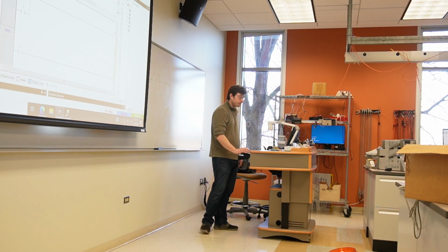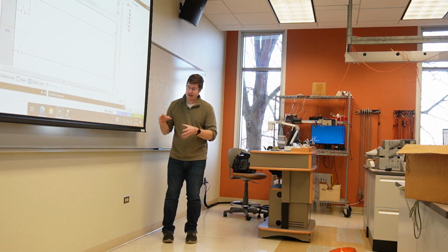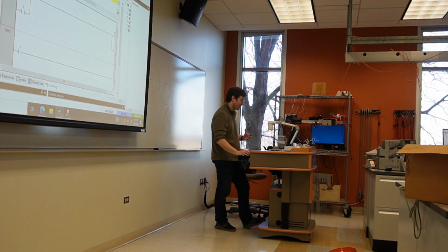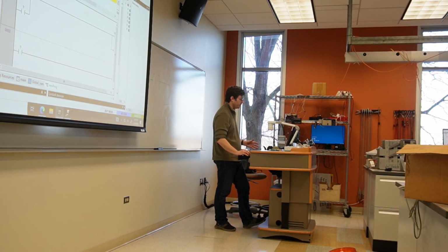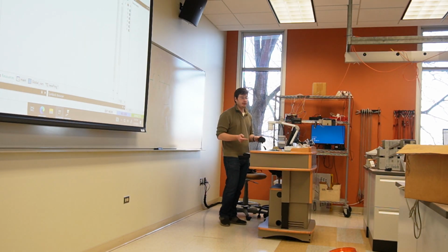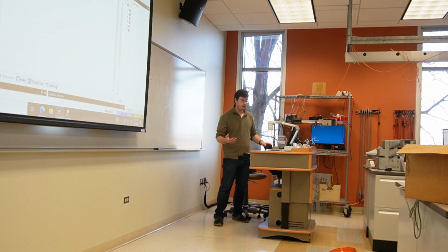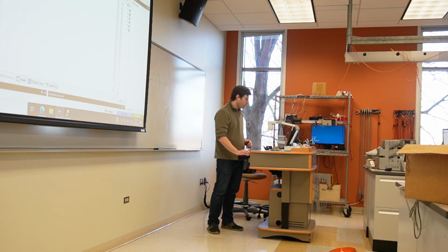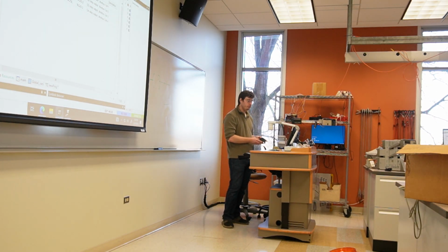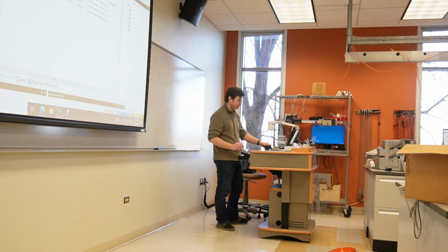All right. One more thing, bridging the gap between virtual reality and real reality, right? So how do we, if we set output 1 on, get it to turn on a relay, for example? That's done in our resources tab. So right underneath our project window is a resources tab. Here is where we assign what does I1 mean? What does relay 2 control? Yada, yada, okay? So starting off, our relay outputs are right here. So I just clicked on that once and it brought up this window. And now we can assign variables to each of our outputs, O1 through O4. O1 being relay 1, O4 being relay 4.